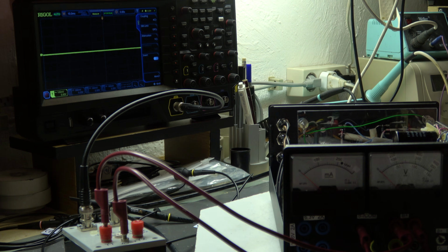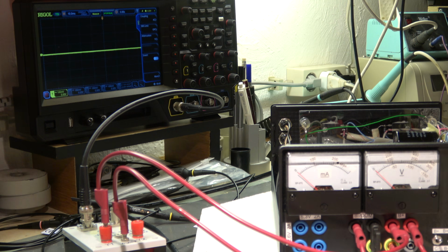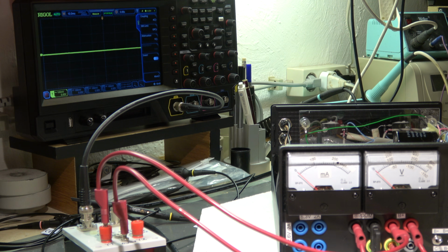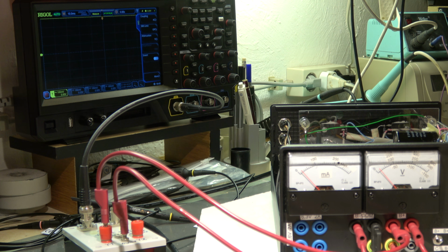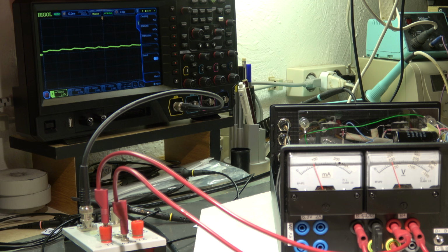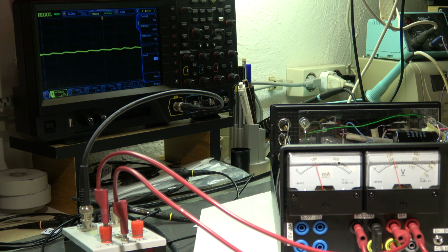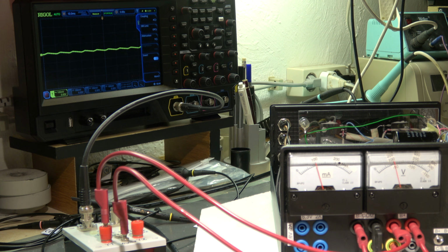We have full load. We're using 100 millivolt per division, increasing the output voltage up to 200 volt now. We see there's a small ripple. Current is 100 milliamps, the ripple is in the range of 50 millivolt peak or less. With increasing voltage, the ripple increases a little bit. And here, as we come into the region of the limit of the power transformer, the ripple increases.